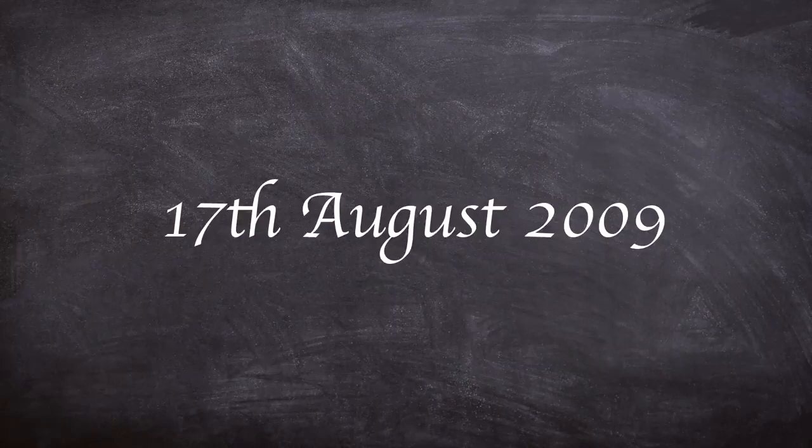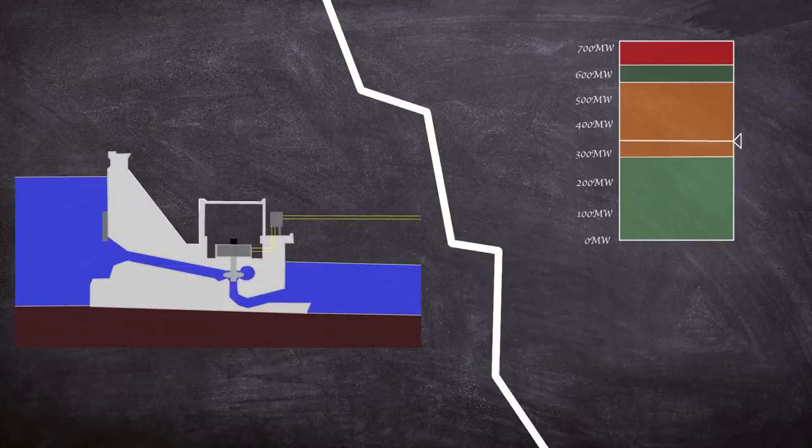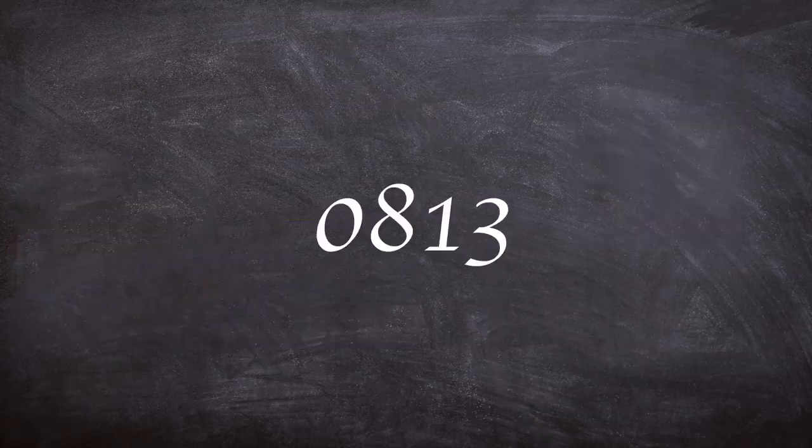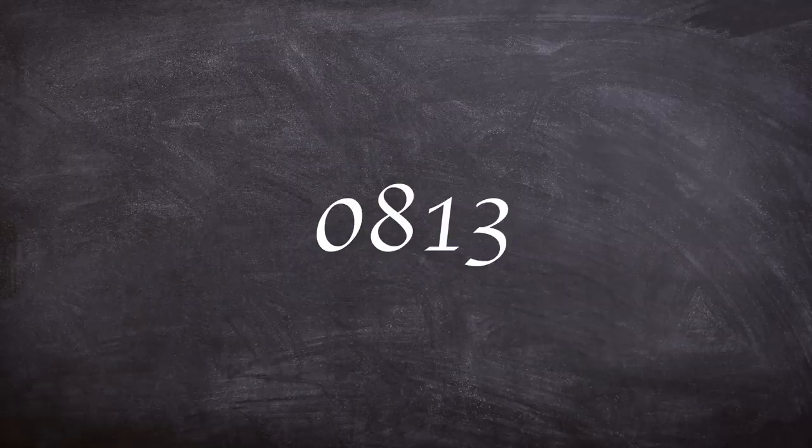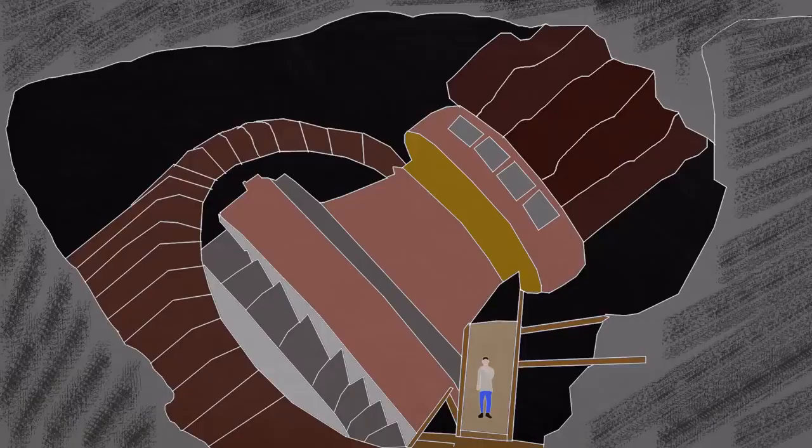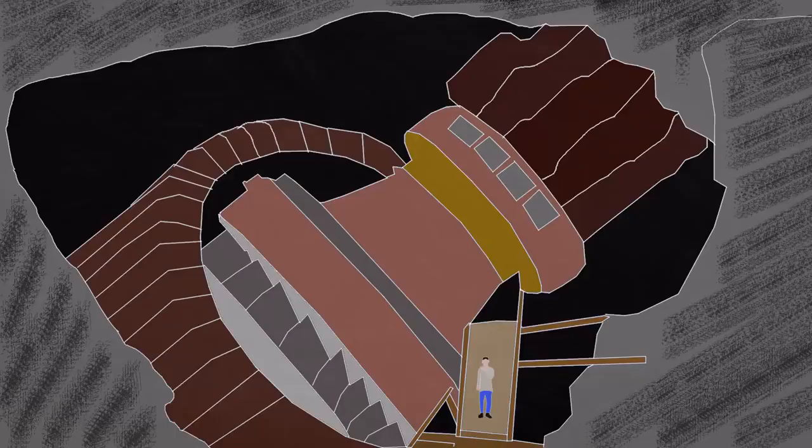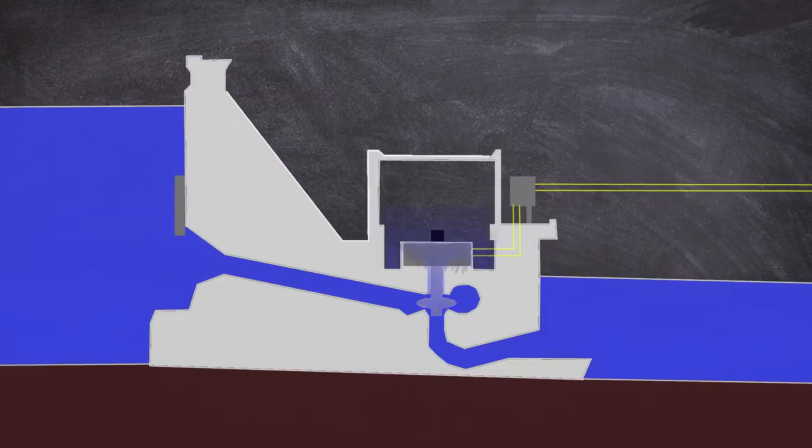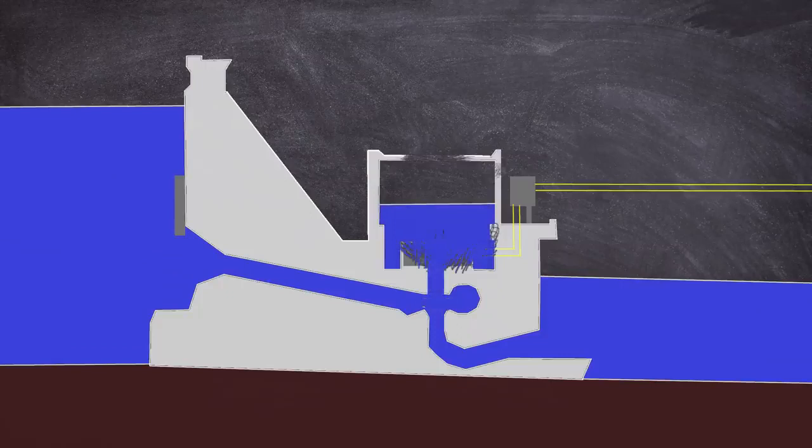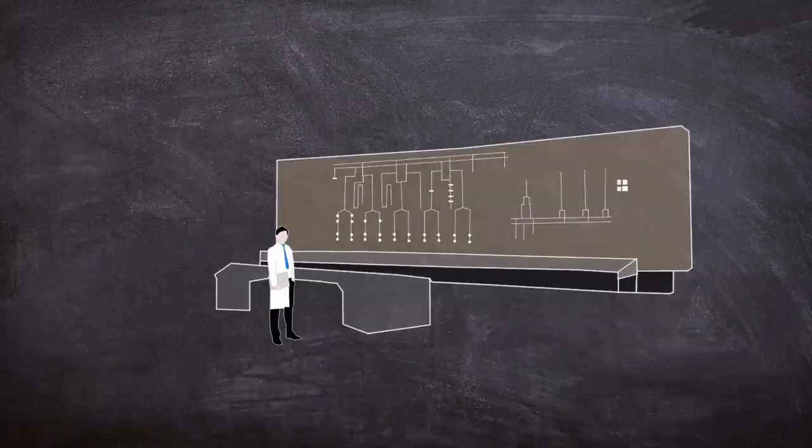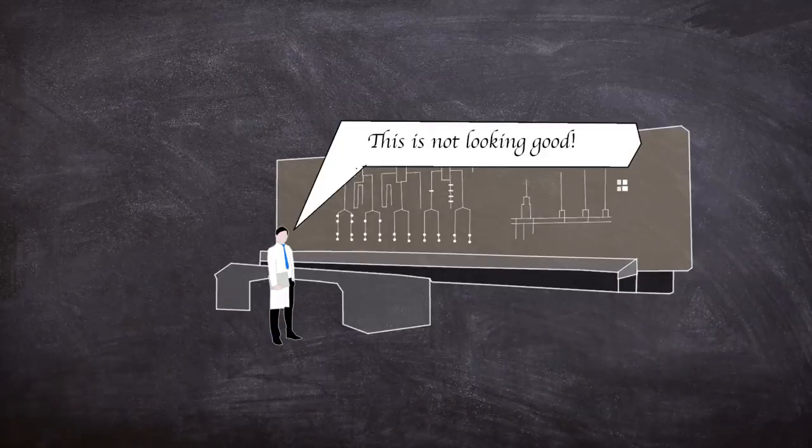On the morning of the 17th, the output of unit 2 varied widely, and because of this it sat for too long in the dangerous Band 2, aka the not recommended zone. The turbine began to vibrate, in doing so weakening its internal components. At 8:13 a.m., a loud bang rang out in the turbine hall. The turbine cover shot up, followed by the 920-tonne rotor. The rotor, still spinning, flew across the gallery, destroying everything in its wake. The turbine was ejected from its pit under the 20 atmospheres of water pressure, exposing the penstock. Essentially, there was now no barrier between the force of the reservoir water and the turbine hall.